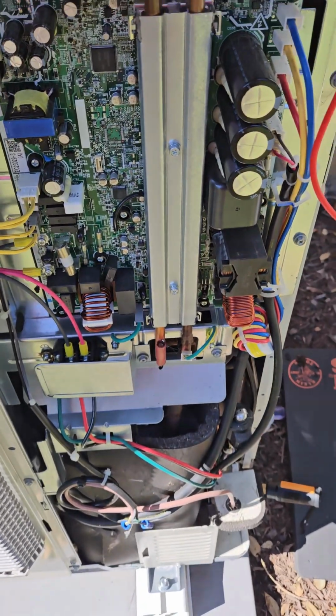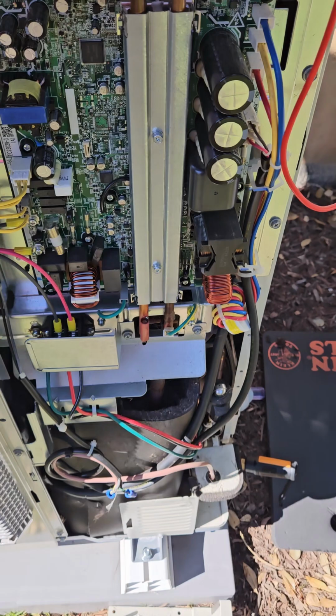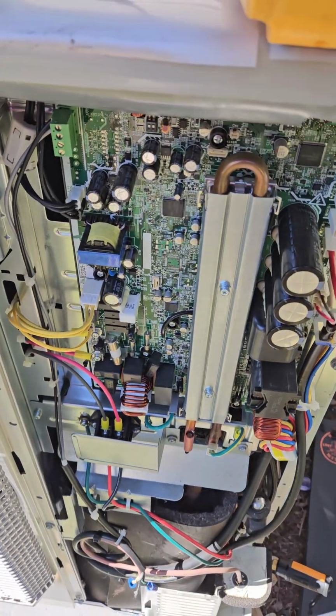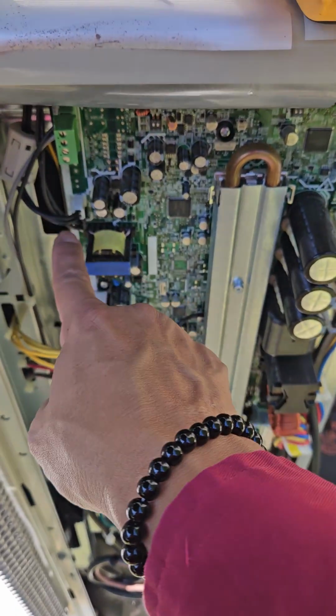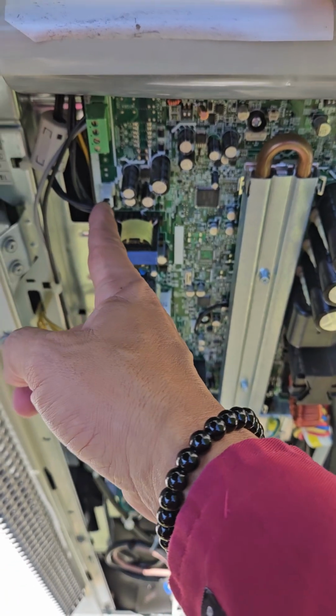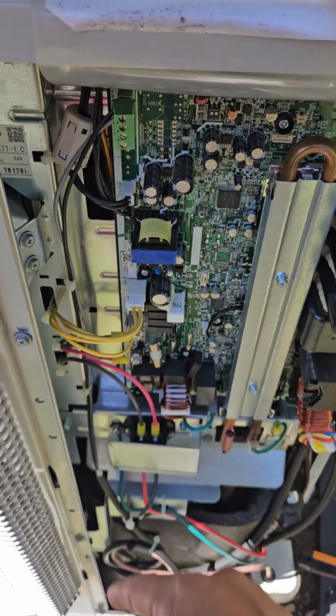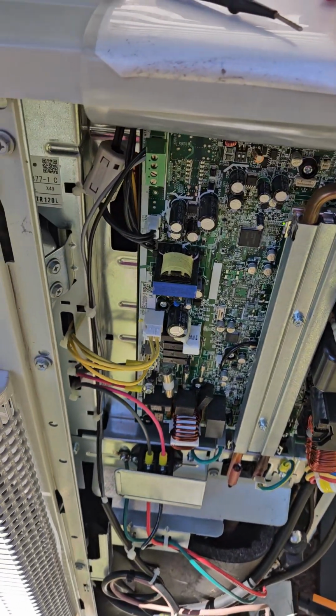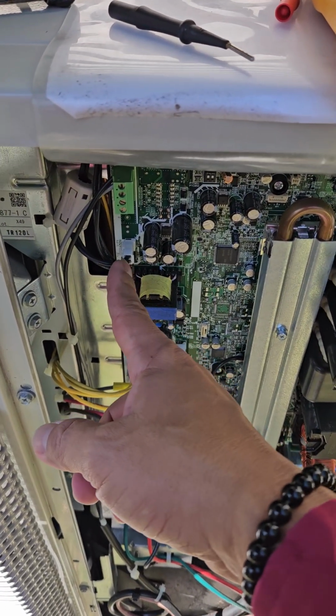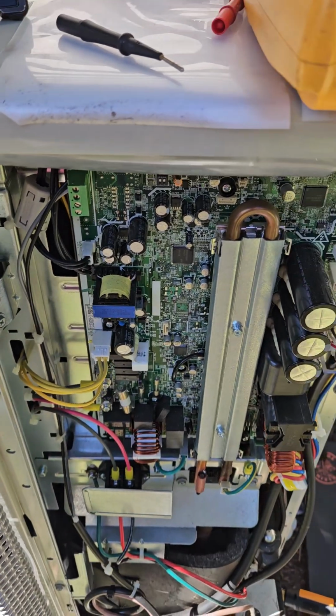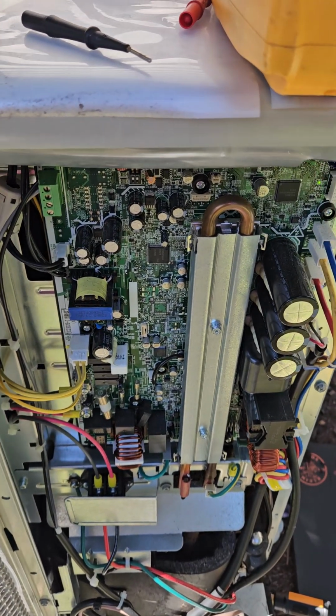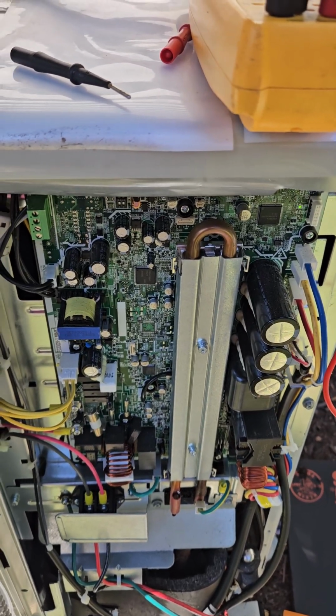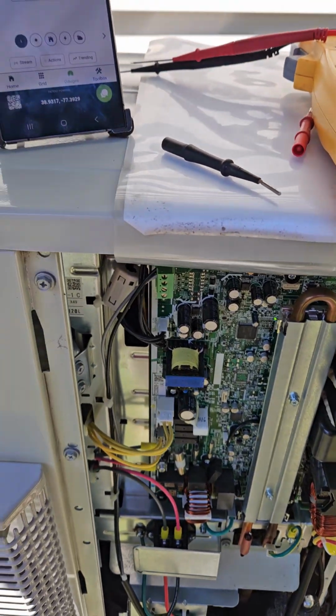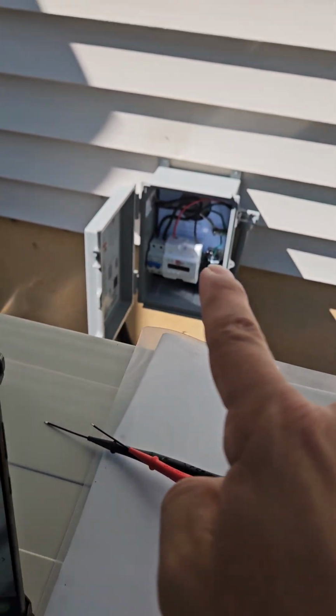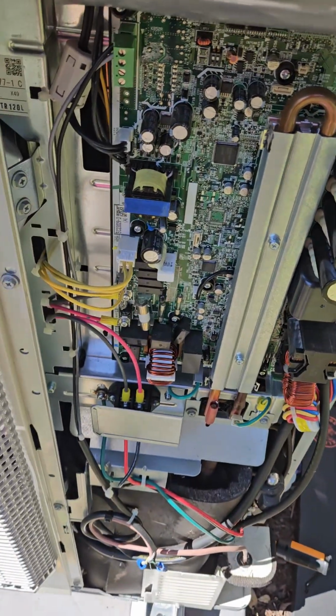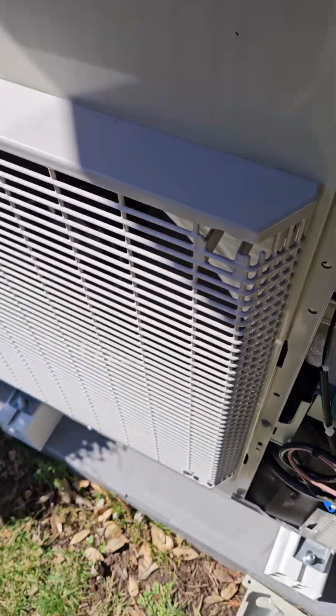Okay, here we go. The unit was in lockout on code 13 with the high pressure. So what I did was, before I reset it, I checked the resistance on the high pressure switch right here. Well, it's not a switch, but a thermistor, and I was getting some resistance, so it wasn't open or low. And then I checked the voltage coming out, and it was 0 DC volts. So that was telling the unit that it wasn't sending any voltage to the actual pressure sensor. So I cycled the unit back on, so I reset the monitor control that we have there, and I was able to reset the code. Now it's up and running in heating mode.